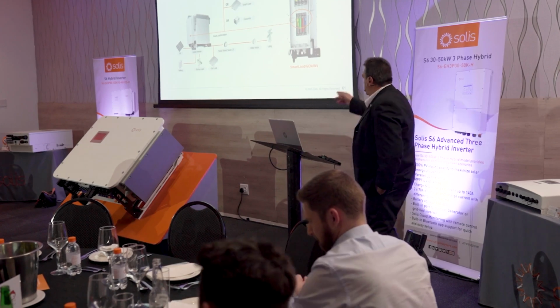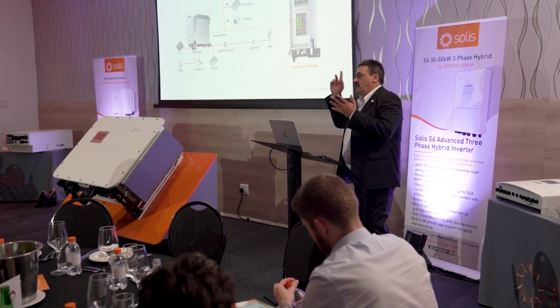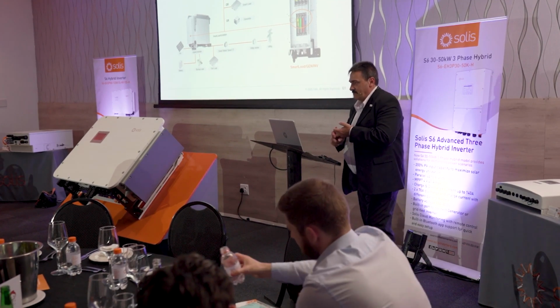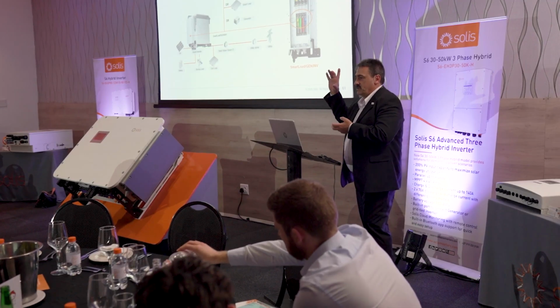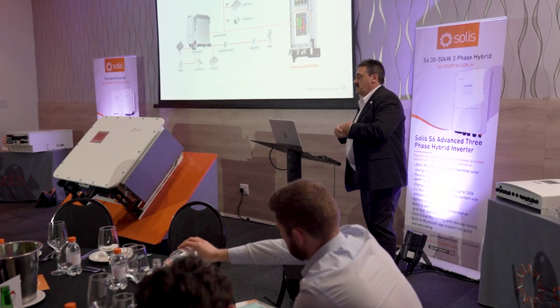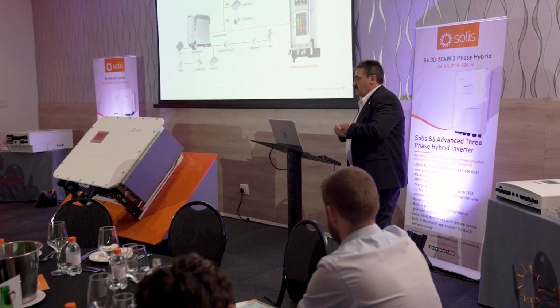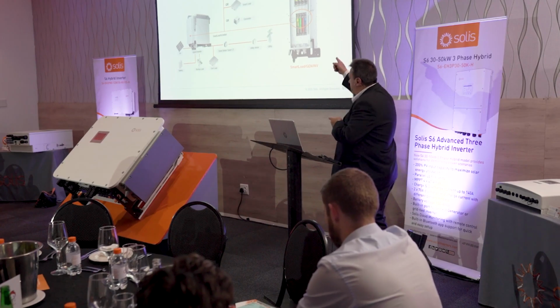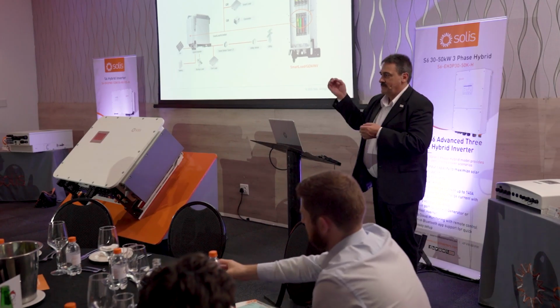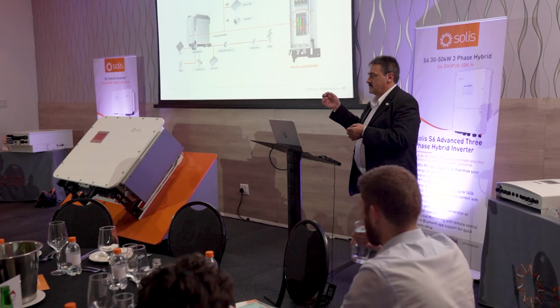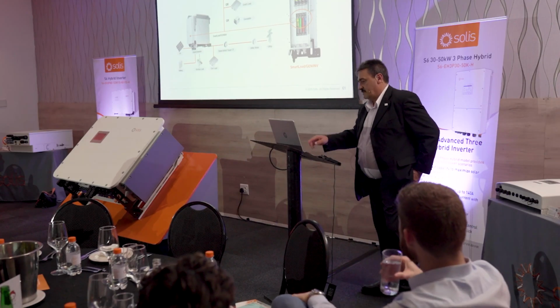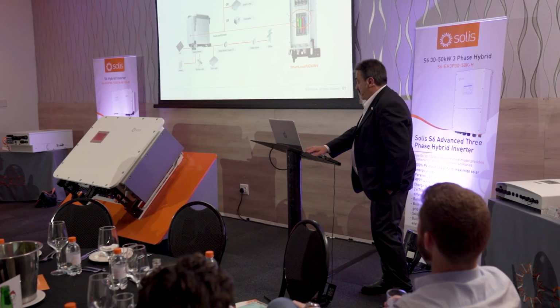So on the home run, and especially now that you're changing to aluminium cable, what happens with aluminium compared to copper? The size immediately needs to go up. And also if you're using aluminium, use bimetallic lugs, copper aluminium lugs. Because we see a lot of problems caused by that as well.